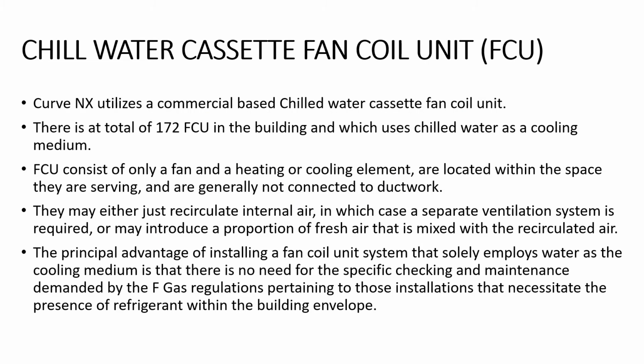So, chilled water cassette fan coil unit, FCU, fan coil unit. Curve NX utilizes a commercial-based chilled water cassette fan coil unit, FCU. There is a total of 172 FCU in the building, which uses chilled water as a cooling medium. FCU consists of only a fan and a heating or cooling element, which is located within the space they are serving, and generally not connected to ductwork. They may either just recirculate internal air, in which case a separate ventilation system is required, or may introduce a proportion of fresh air that is mixed with the recirculated air.